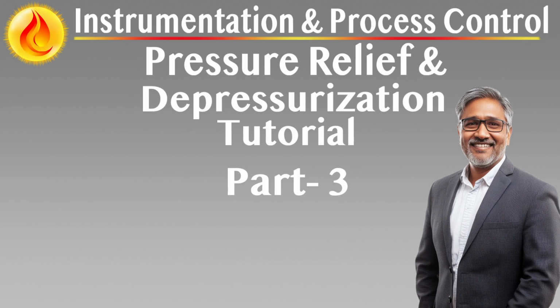Assumptions regarding fire protection. Active fire protection systems, e.g. deluge, are standard, but their operation cannot be guaranteed, so they must not be credited in sizing calculations. Passive protection, e.g. fireproof insulation, may be considered if properly verified.